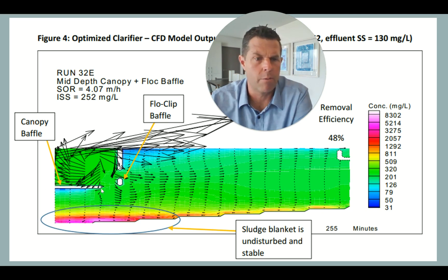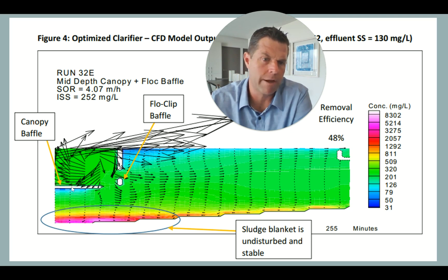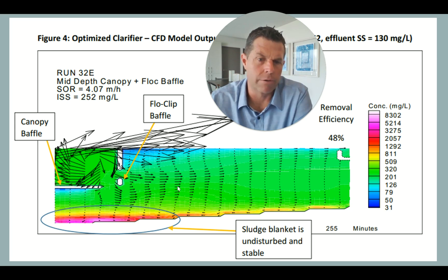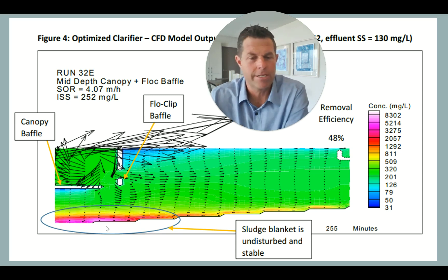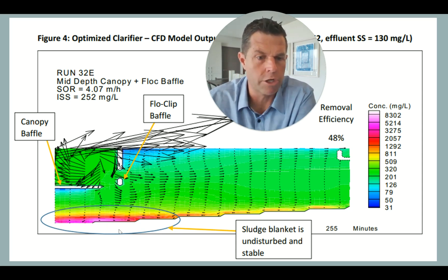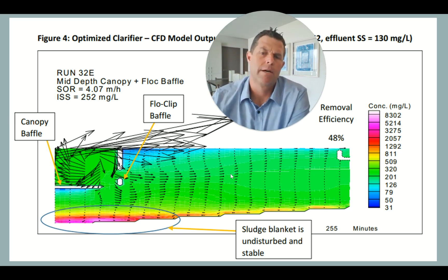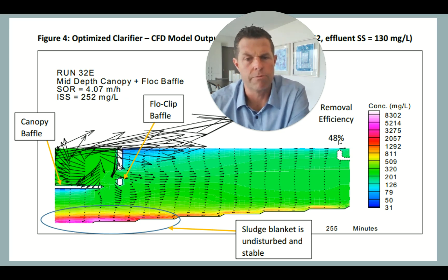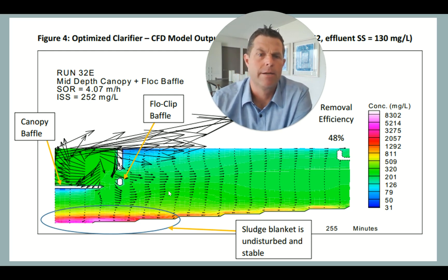We then modeled some improvements. There's a system that we design and sell called a canopy baffle — we place that here — as well as a flocculation baffle, which helps improve internal flocculation as flow enters the clarifier. We also provide a really good lateral distribution out of the tank. With our x-ray vision, we can see that the sludge blanket is no longer sheared, and we have very high performance even up at 2,400 gallons per day per square foot — still up at 48% solids removal. We improved from 23% to 48% through these improvements.